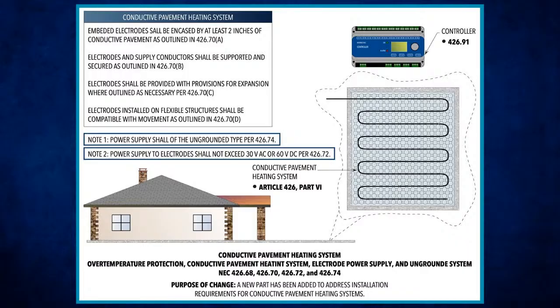There's really no way for me to ensure that that's going to be 100% 2 inches of cover, because a lot of times it floats in the pour. So you put them in those, the bottom I'm showing there. It's really hard to describe when you've actually been out there and done it. You put these chairs on the dirt, and you tie this material. You have different ways of tying this electrode to these chairs, but the chairs will still float. You still have to push them down to the ground while you're pouring, because they'll float. And that was my job.